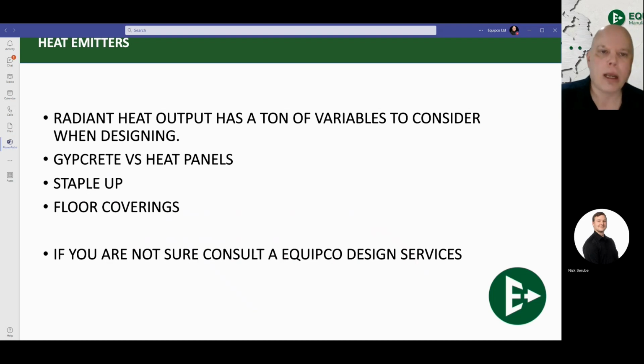It is very susceptible to the installation details. Ton of variables to consider, such as the gypcrete overpour, or is it going to be heat panels? Then we also have, with regards to radiant, our staple up, where we're going in the joist space on the floor underneath to heat the floor above us. That has a tremendous difference from putting the PEX tubing right in the floor of the room that you're in. It needs to be run at a hotter temperature. Heat transfer panels are now nearly required. They're not exactly enforced, but they're an extremely good idea because you need to transfer that heat through a much harder area, which is wood and carpet.